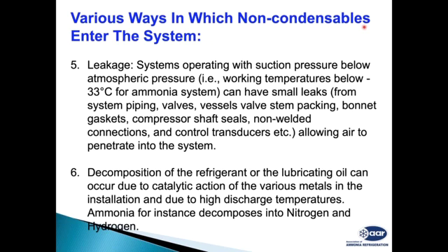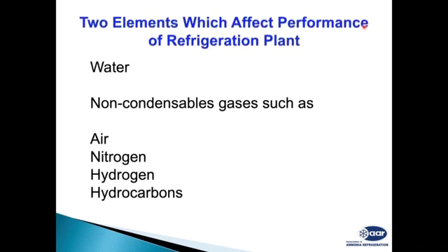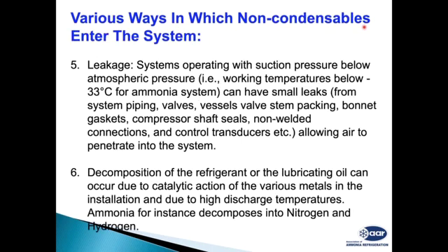And another part is that when there is air in the plant, our discharge temperature increases, which increases the ammonia temperature and also the oil temperature. Many times due to high temperature, oil may decompose, and this decomposition of oil, along with the catalytic action with the metallic parts in the system, will decompose the ammonia, because as we all know, ammonia is made of nitrogen and hydrogen. It will break into nitrogen and hydrogen. Both these gases are non-condensable in our system. Also, the lubricating oil may break, and it will generate hydrocarbons, and some of these hydrocarbons are also non-condensable in our system.